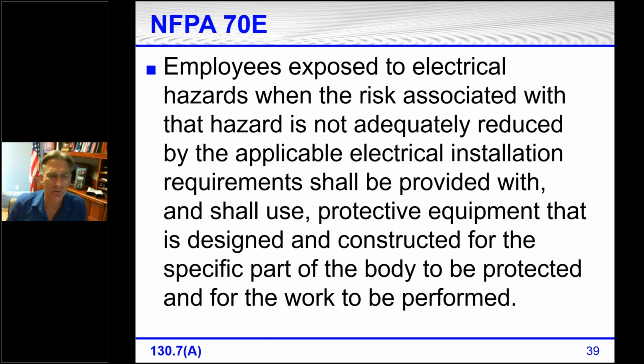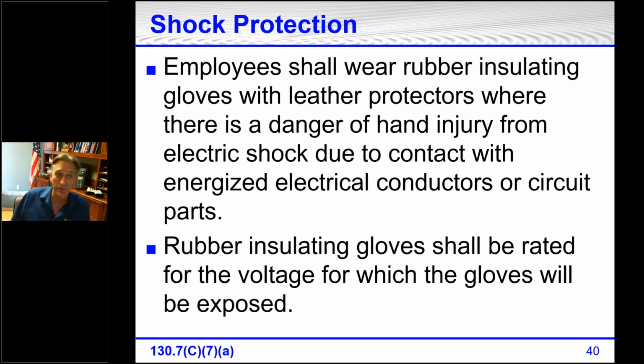70E, employees, okay, this is talking about the PPE. Employees exposed to electrical hazards when the risk associated with that hazard is not adequately reduced by applicable electrical installation requirements have to be provided with and have to use protective equipment that is designed and constructed for the specific parts of the body to be protected and for the work to be performed. Shock protection: employees have to wear rubber insulating gloves with leather protectors where there's a danger of hand injury from electric shock due to contact with energized electrical conductors or circuit parts. Well, the rubber insulating gloves have to be rated for the voltage to which the glove is going to be exposed. Talked about this a while ago.